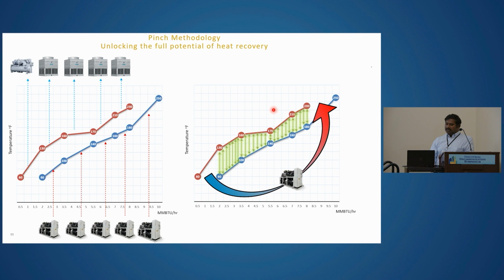So after doing this pinch analysis, we look at the optimized way we are trying to utilize the waste heat available in the facility to heat up the existing process. About 60 to 70% of the waste heat from the process went into the atmosphere with the help of a cooling tower or a chiller. Why can't we put that back into the same process and optimize with one or two heat pumps?